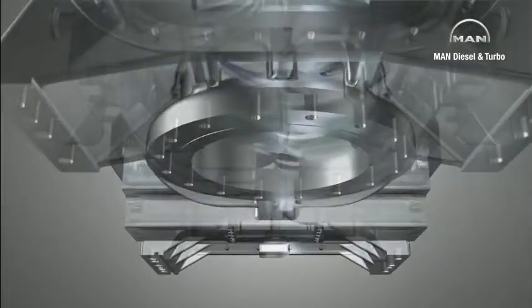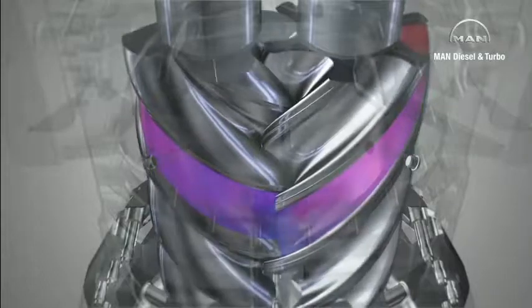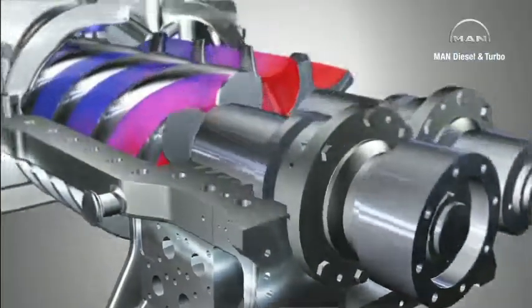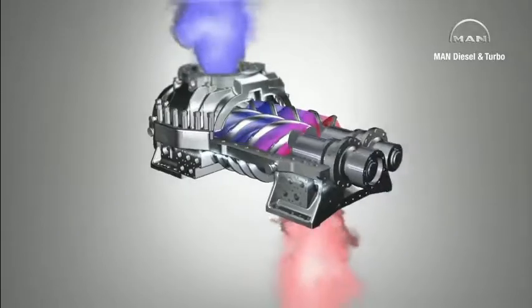The only major disadvantage of screw compressors is that in order to maintain a seal between the rotors, oil must be injected onto the compressor element during the compression of the air. This oil is later removed by an oil separator so that we end up with clean compressed air.